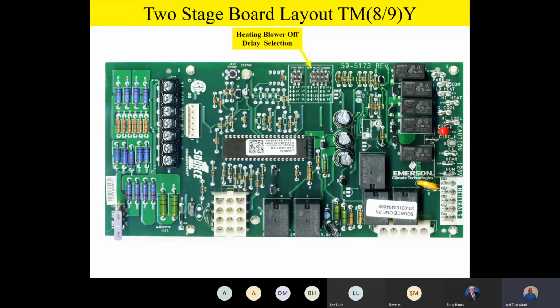Right next to that, you have your heating blower off delay. Again, these are dip switches. And you'll see, if you look at the little diagram there, based on the position of those switches, we have 60, 90, 120, or 180 second heating off delay. Now remember, team, all of our boards are set up for a factory on delay of 30 seconds. So once we get flame proving on a heating call, 30 seconds later, the indoor fan comes on. That's factory set, you can't change it. However, the heating off delay you can change with those switches.